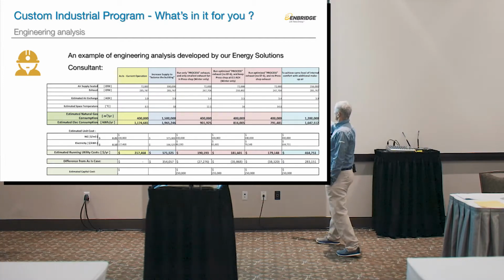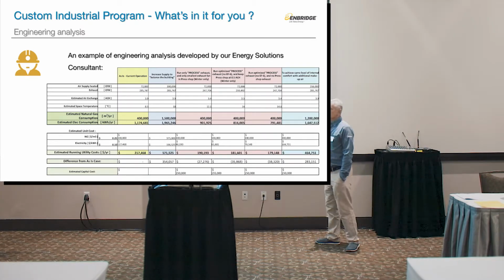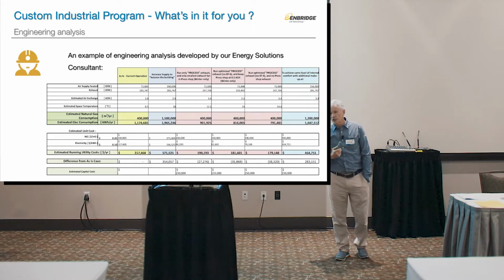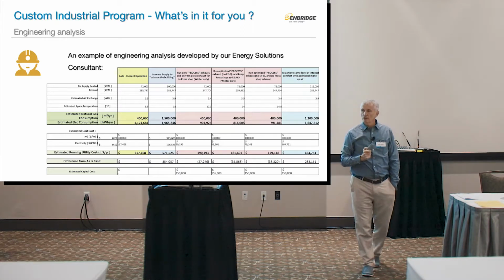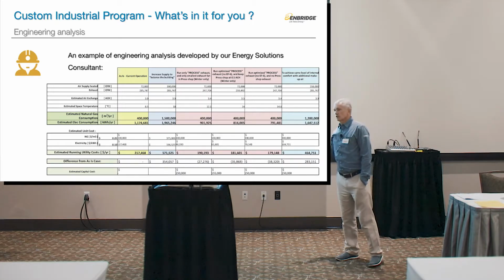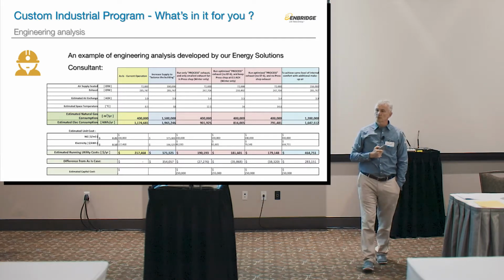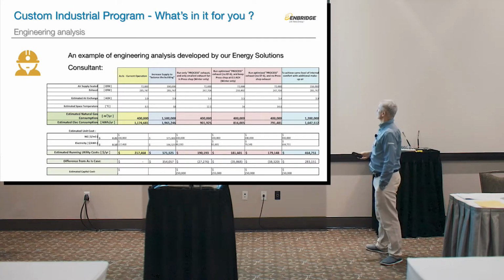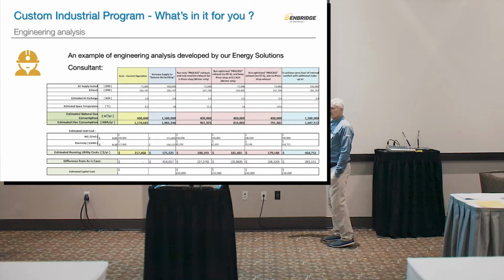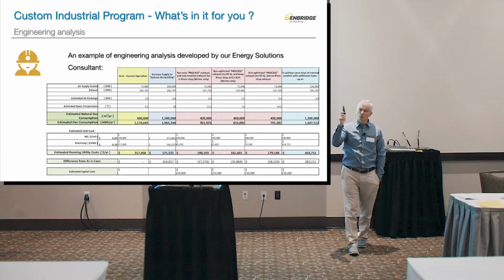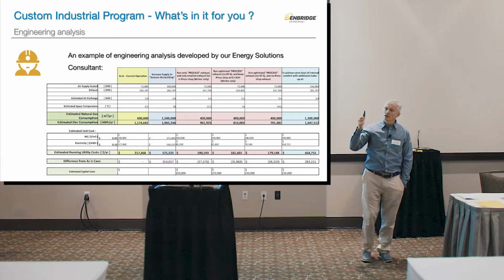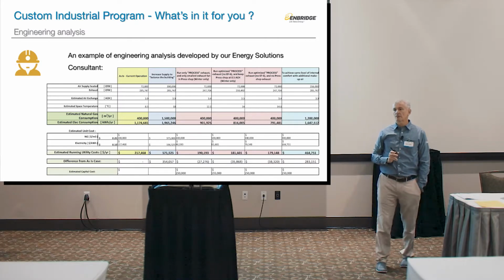They chose this one, and we checked on them two years later. They're actually not using 400,000, they're using 275,000 cubic meters, because not only did they reduce the exhaust, they also tied the exhaust to their process. So if the process doesn't run, the exhaust doesn't run, which further reduced their makeup air requirements.